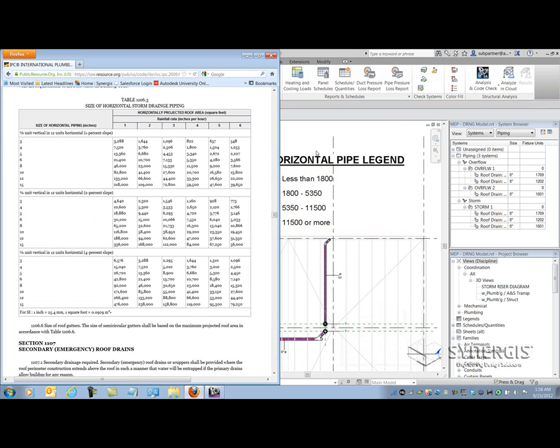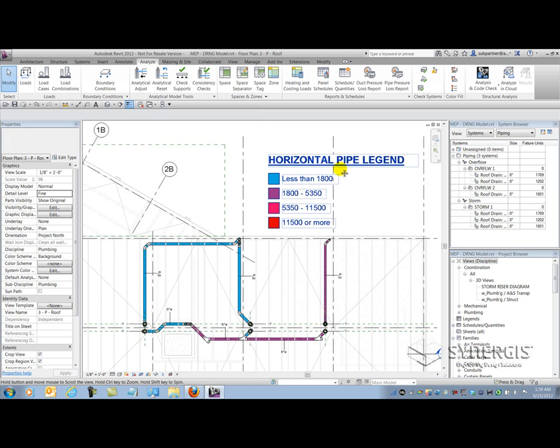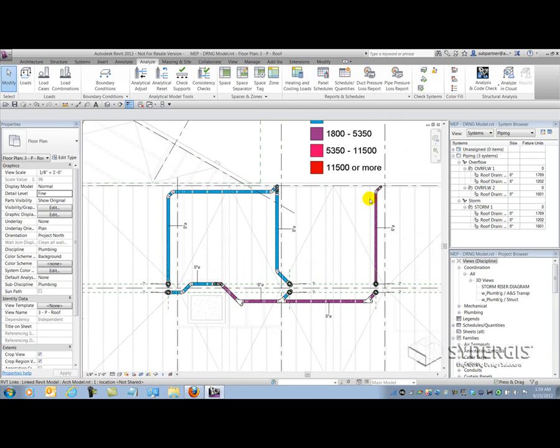Looking at the chart for four inches of rainfall: 1800 square feet is going to be a four-inch pipe. For 5350 and up it's going to be an 11,500 square foot range — a six-inch pipe. And then for anything above that, it'll be eight-inch pipe and so on. That's how I can use the software to give me some idea of what pipe sizes I have to work with. Here I can see I'm probably going to need six-inch pipe for this magenta/deep purple color.